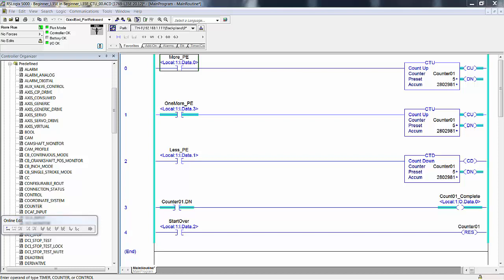So you could have 7 conveyors running parts into a bin, and you want to count the parts into the bin. And you have 7 different subroutines, one for each of the conveyors. And then you have logic that selects only one subroutine to execute. If this additional rung right here was in another subroutine and it was not being executed, then the counter data type would never see the false state. It would only see this rung.